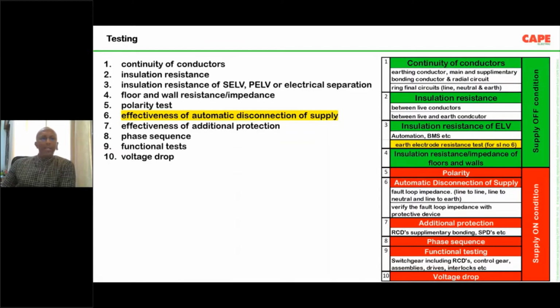The idea is that every building, after erection, while commissioning, or once the electrical system is put into service, we are supposed to do this particular testing. For every building, we are supposed to ensure that electrical safety is achieved by making the inspection and testing. Now the interesting point here is, out of the 10 tests, about 4 are in supply off condition and the balance 6 are in supply on condition.